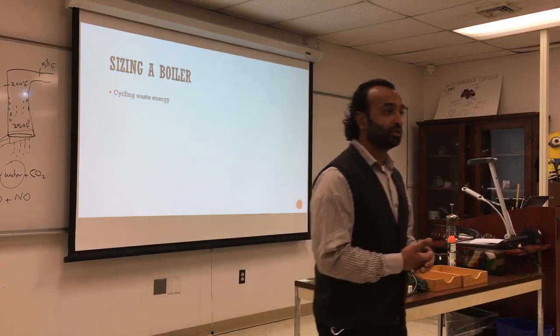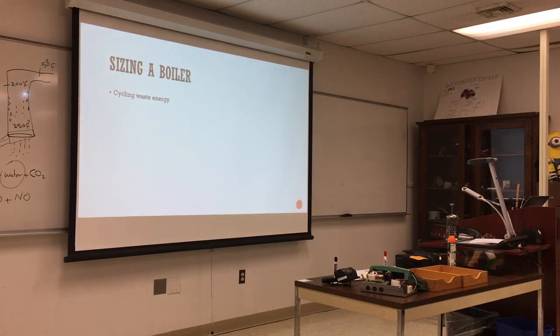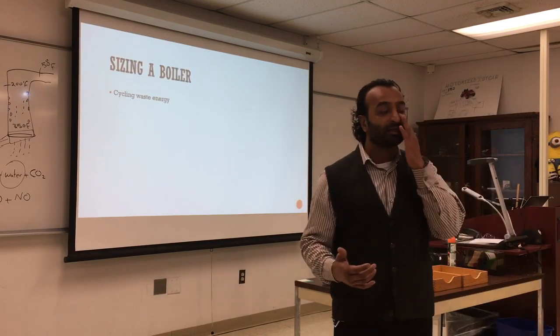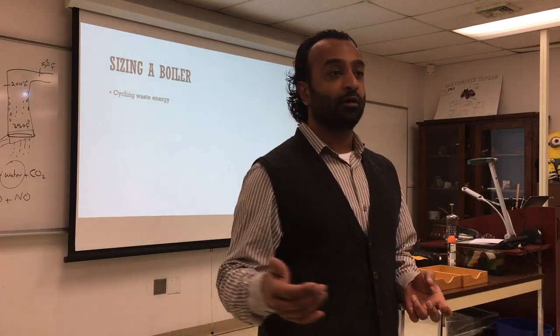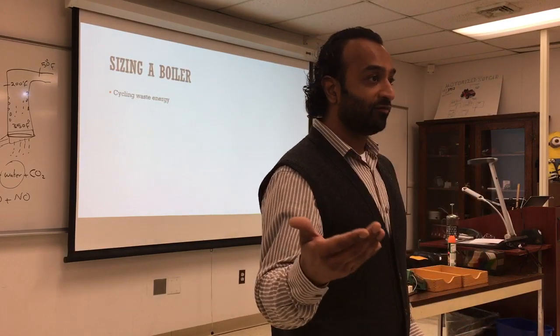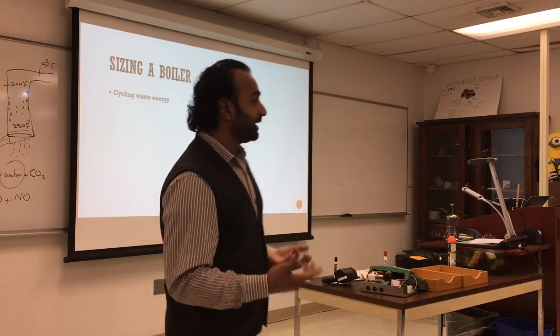You don't want too much cycling. It's different if you just turn it on once a day and that's it. But if it cycles every hour, that's a lot of losses. All the heat can go either to the basement or to the outside. Also, the heat is coming all the way from the basement, so when it goes to the 3rd floor, 2nd floor, you lose some on the way. So the less cycling, the better.